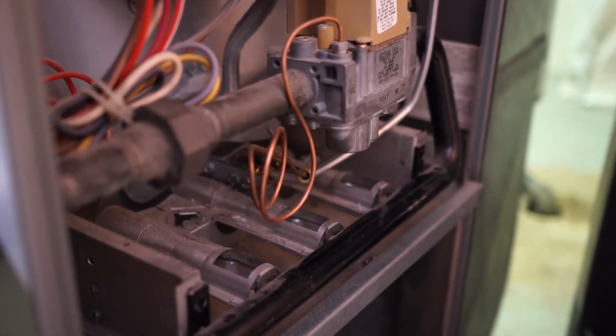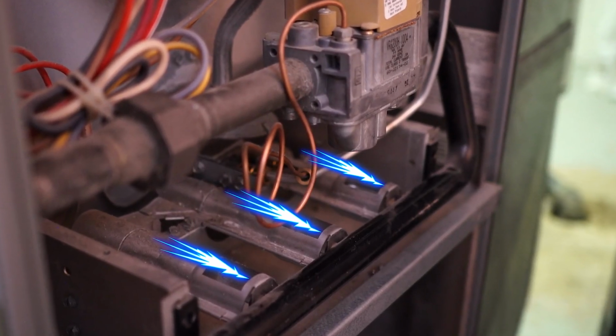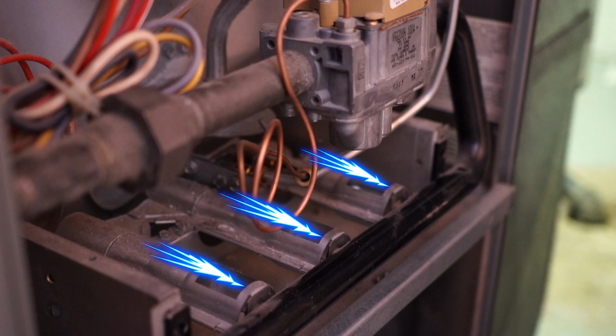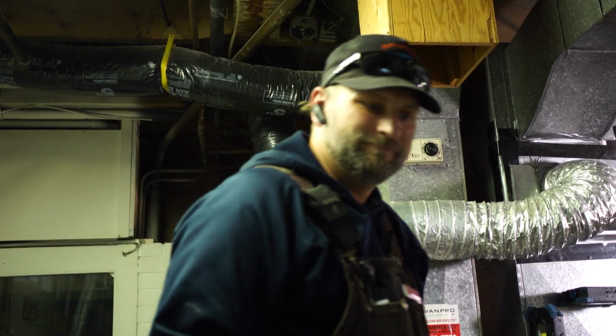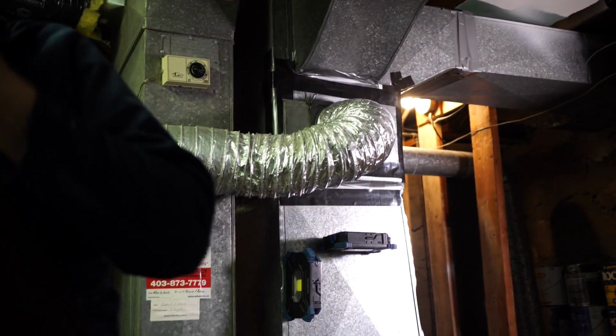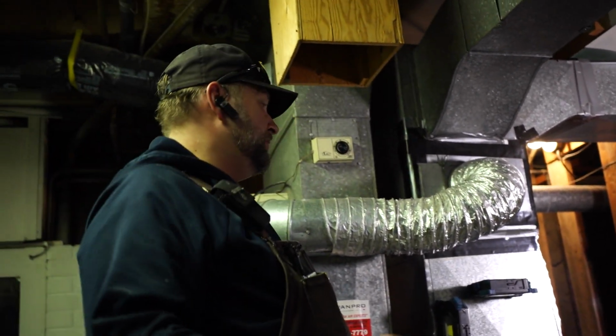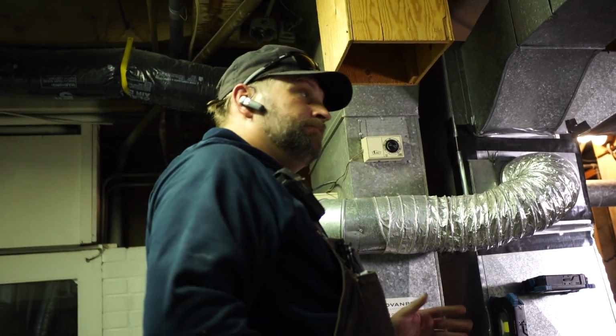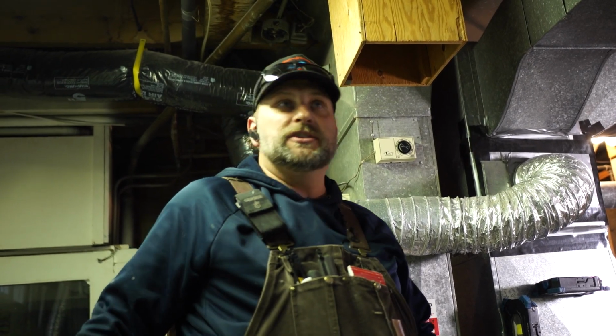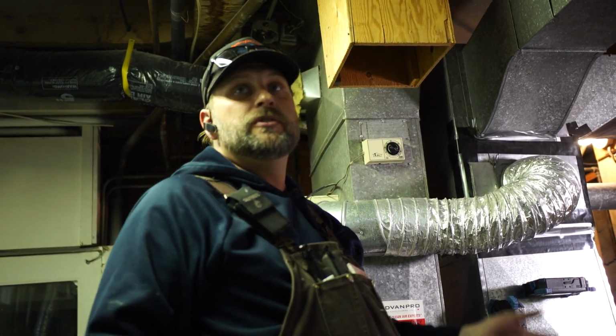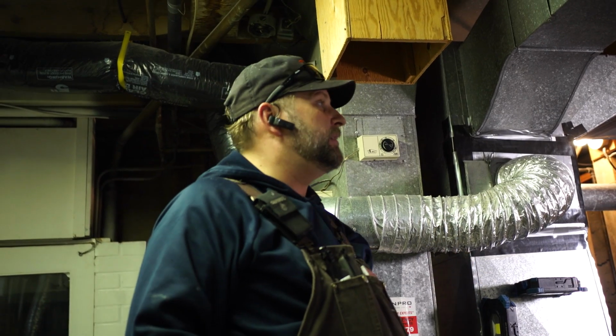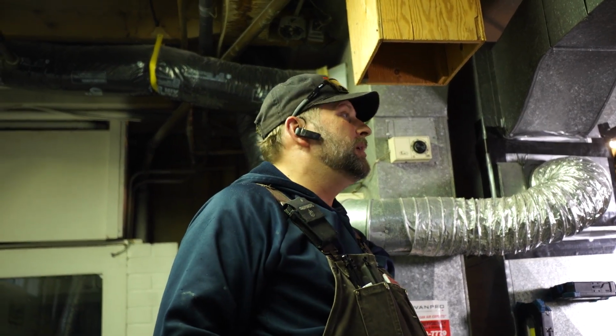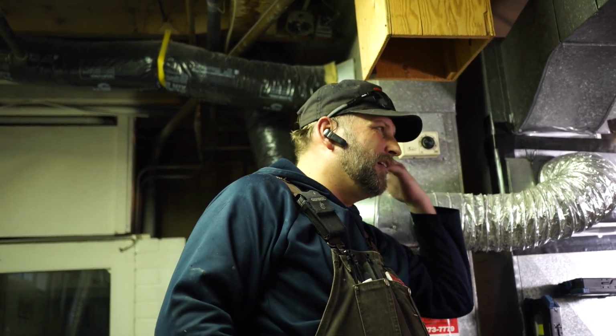We now repaired the plug in the burner assembly, and we have 3 solid blue jets running into the heat exchanger. Beautiful. How's the motor sound? Sounds great. Another big thing - no squeaking, no rattling. Amperage draw is something I check on both motors, the inducer and the blower, and that's the biggest indicator of whether a motor is going to go, besides smoking and audio.